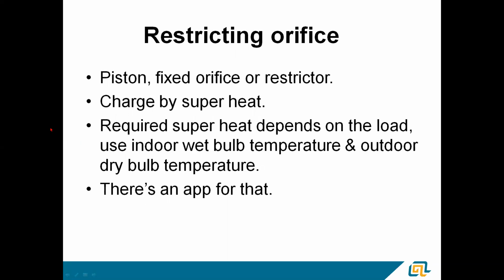Restricting orifices, as I say, they are making a comeback. I'm seeing more and more of them. It can either be referred to as a piston, a fixed orifice, or a restrictor, all the same thing. Charge these by superheat. Do not charge them by subcooling. They are charged by their superheat. The required superheat depends upon the load. So you use your indoor wet bulb temperature and your outdoor dry bulb temperature, and you figure out what your superheat should be.